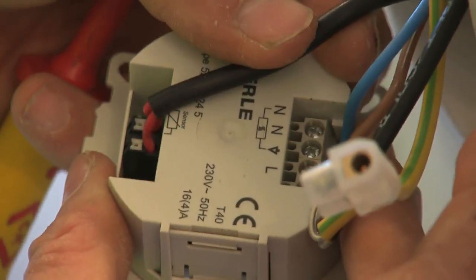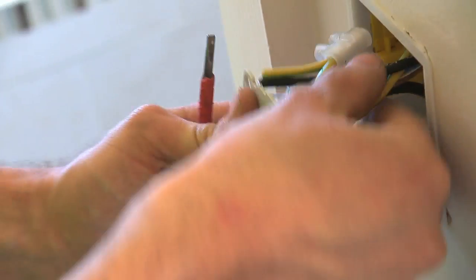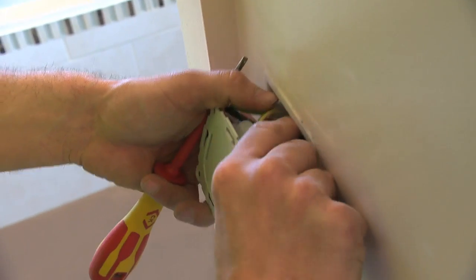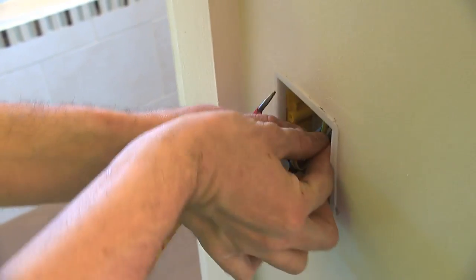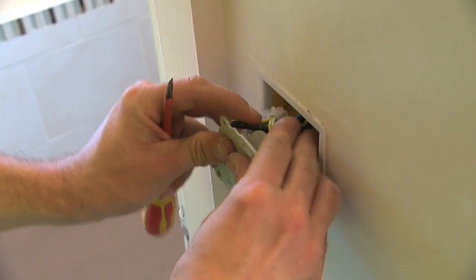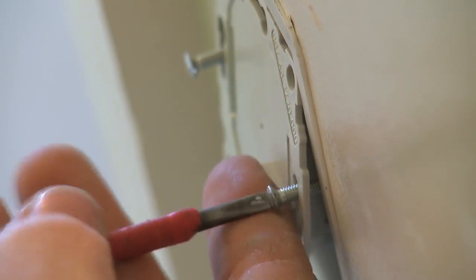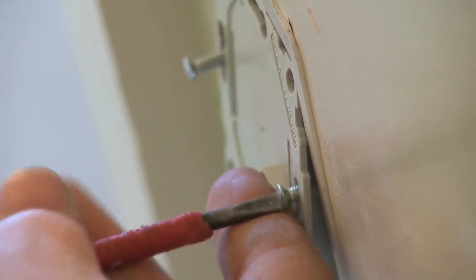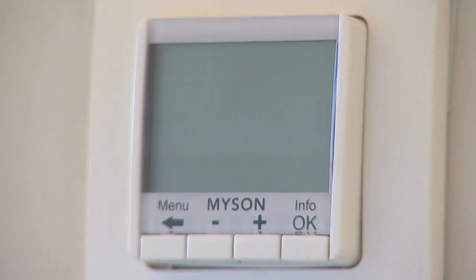Firstly, make sure you have disconnected the electric circuit from the supply. Your room thermostat should be mounted in a position where it is easy to access and operate. Your thermostat comes supplied with an instruction sheet and wiring diagram and should be connected in accordance with the wiring diagram as demonstrated here. Then fix the fascia to the front as shown here.